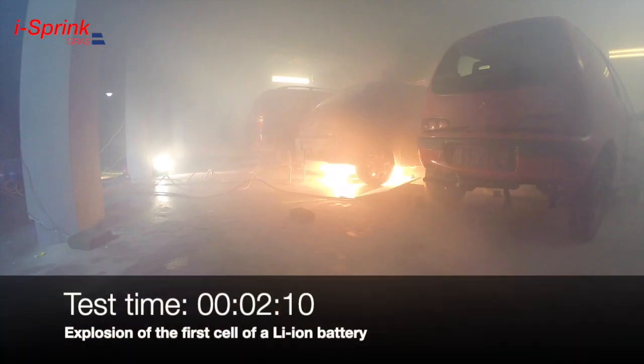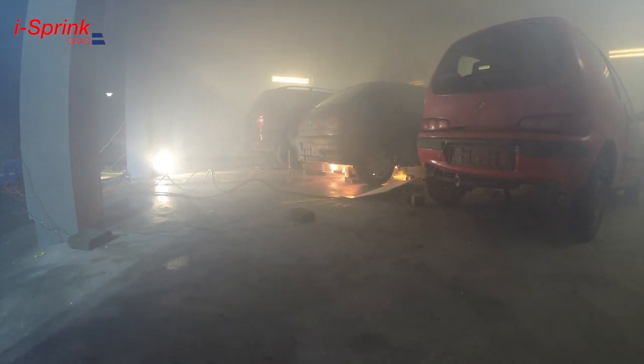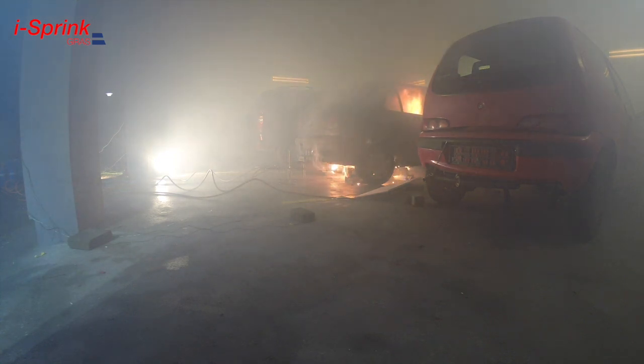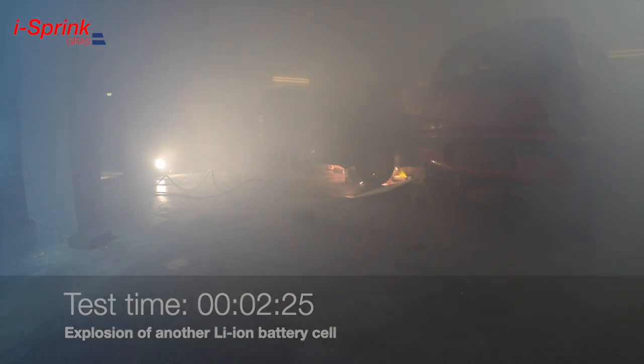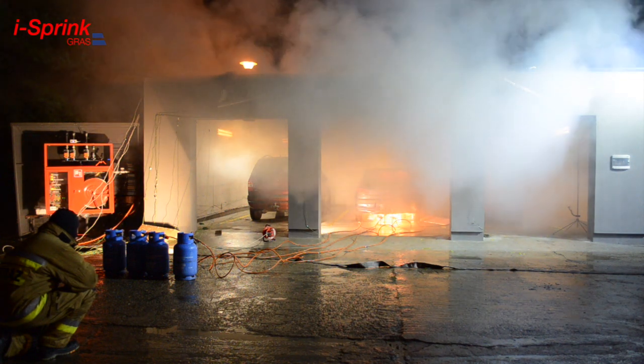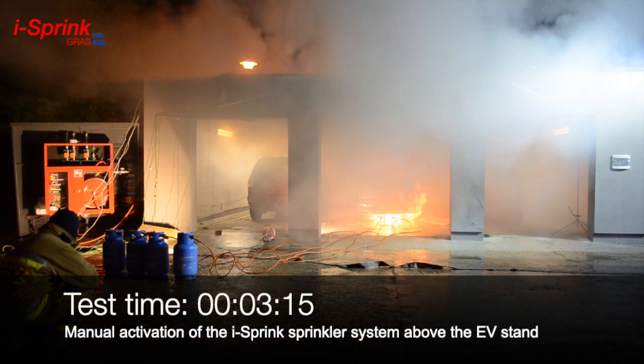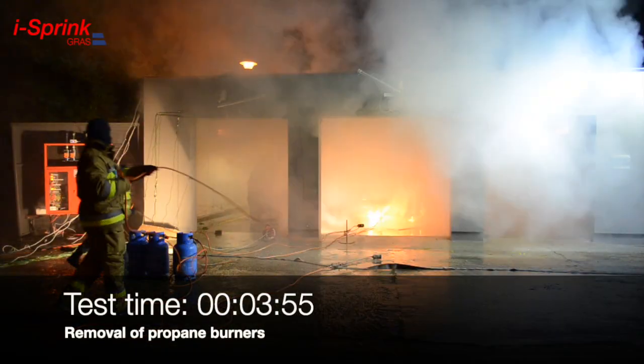The explosion of the first cell of a lithium-ion battery immediately ignites the outer parts of the vehicle body. An explosion of another lithium-ion battery cell follows. The achieved power of the fire causes its self-spreading; accordingly, the i-Sprink sprinkler system above the EV stand is now manually activated. Propane burners are then removed.